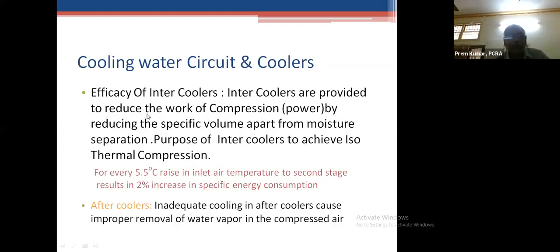So the efficacy of intercoolers is more important because the compressor is very hot. For every 5.5 degrees of inlet temperature, a 2% increase will be there. So the cooling circuit is important. Where intercoolers and aftercoolers are used, there will be no saving, but of course the moisture reduction will be there, and the compressed air quality can be improved.